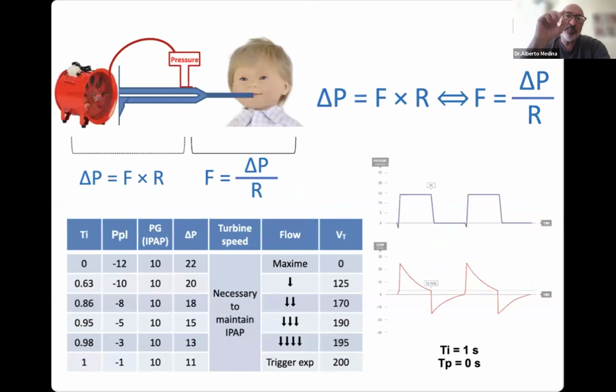The pressure support needs different things to set. The first one is the inspiratory trigger. The inspiratory trigger detects the inspiratory effort of the patient. The turbine is working like this. This velocity of the turbine maintains the lower pressure, the EPAP. But once the ventilator detects the effort of the patient, using the inspiratory trigger, the velocity of the turbine is going to change from this point to this point. And we can move from one velocity to the other like this or like that.